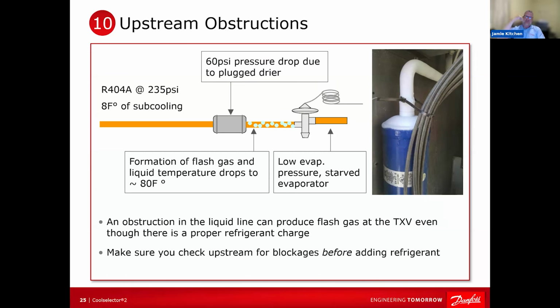All right, it's now time for upstream obstructions. This kind of falls under, it's not the TXV. Think back to tech school, high school, electrical, right? You've got 24 volts, or probably 26 volts, at your control transformer. You've got 0 volts at your relay coil, and there's supposed to be voltage there. What do you do? You figure out where the voltage went, right? So you hopscotch until you see that voltage differential that tells you something is open, all right?